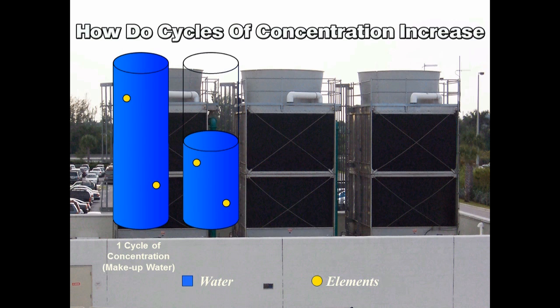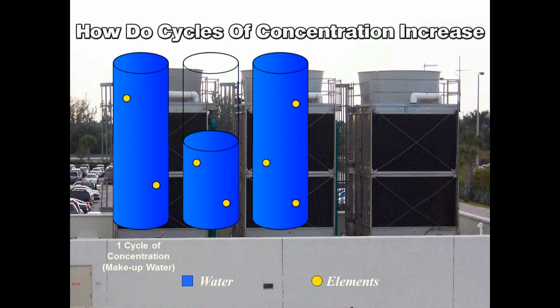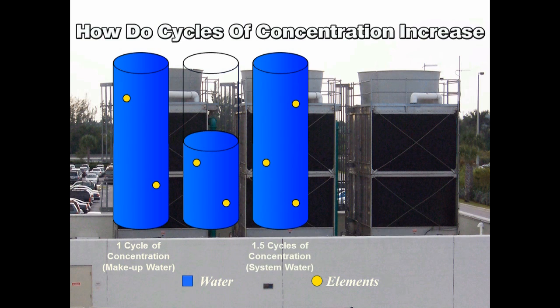Fresh makeup water is added to the tower to replace the water that evaporated. This also adds 50% more elements to the tower water, increasing its concentration to one and a half times that of the makeup water. The tower is now said to be at one and a half cycles of concentration.